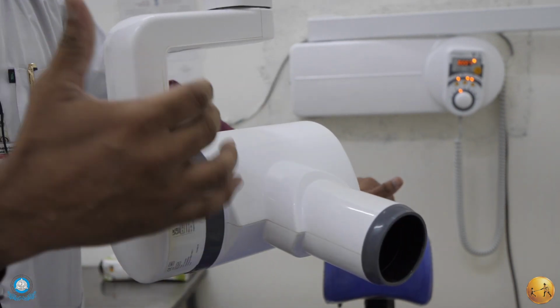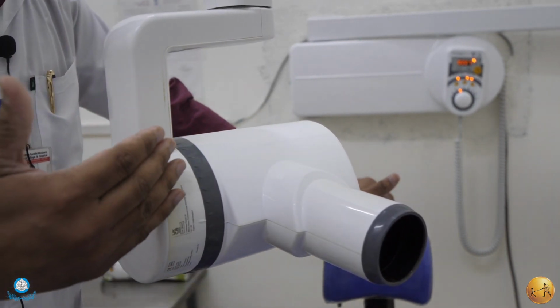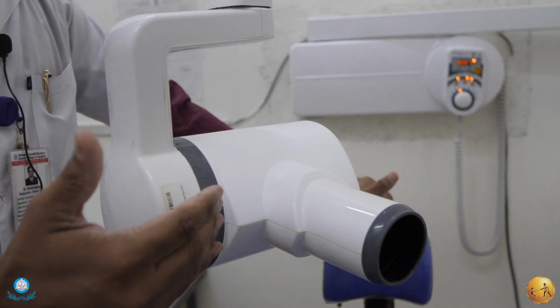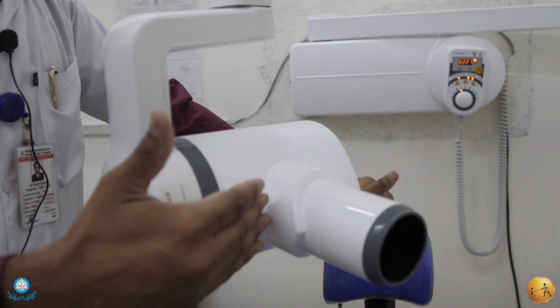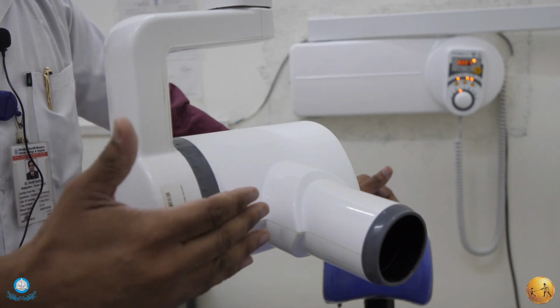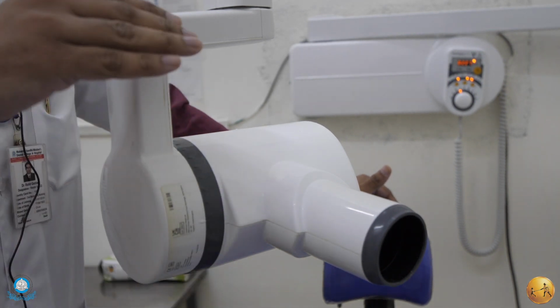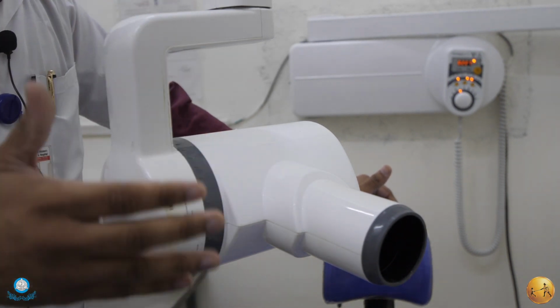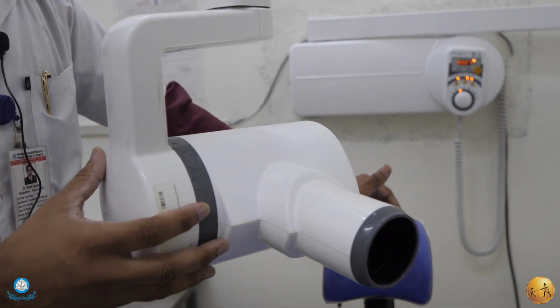Now these X-rays, once produced from a tube, have to pass through tube head seal. Then collimator, which is made of lead. Now function of collimator is to restrict the size and shape of X-ray beam.